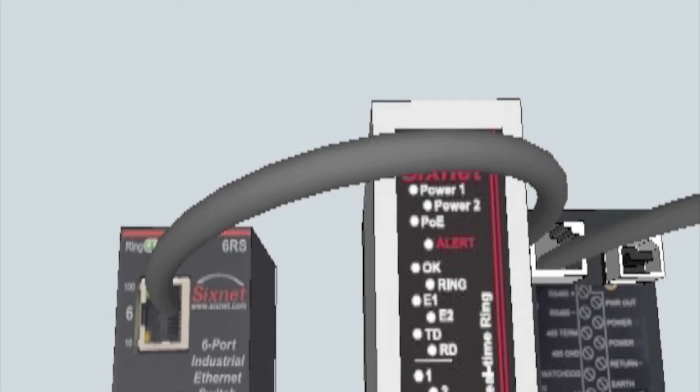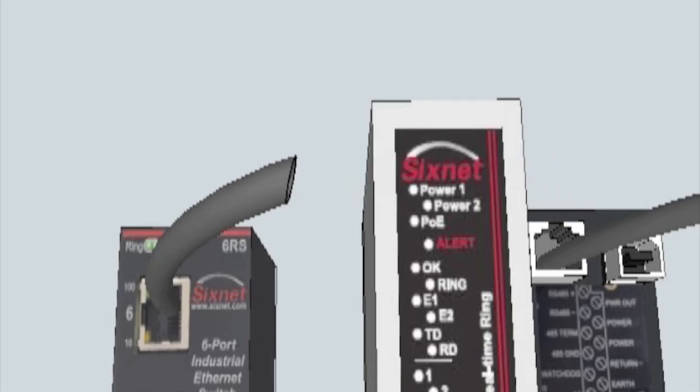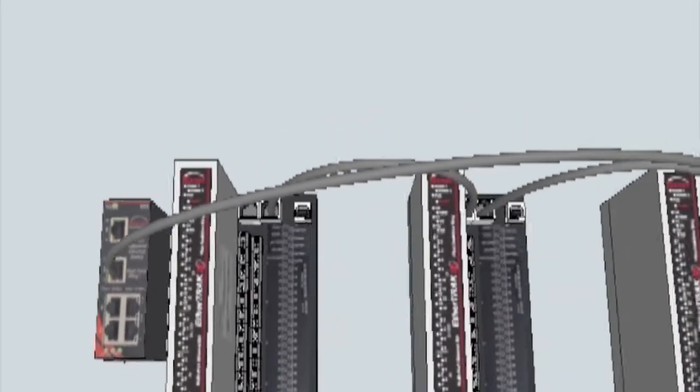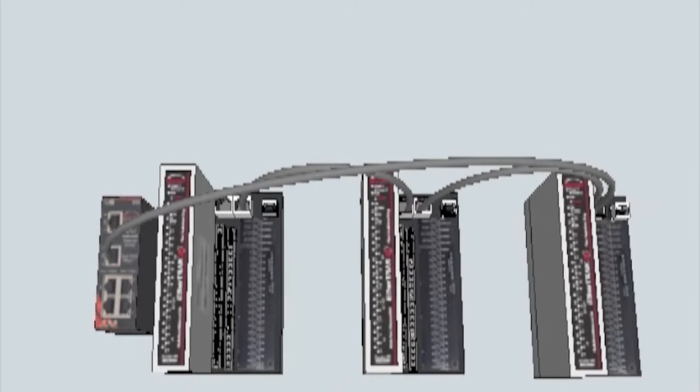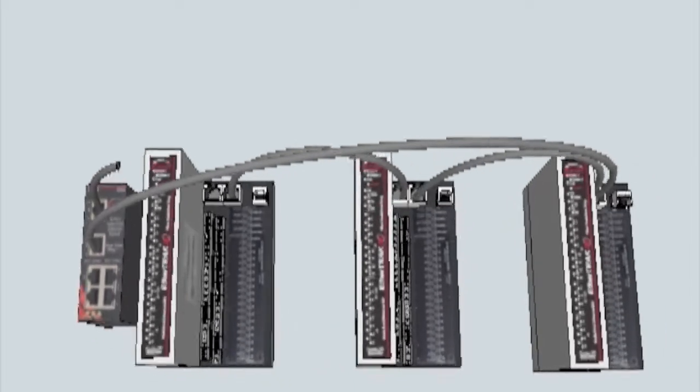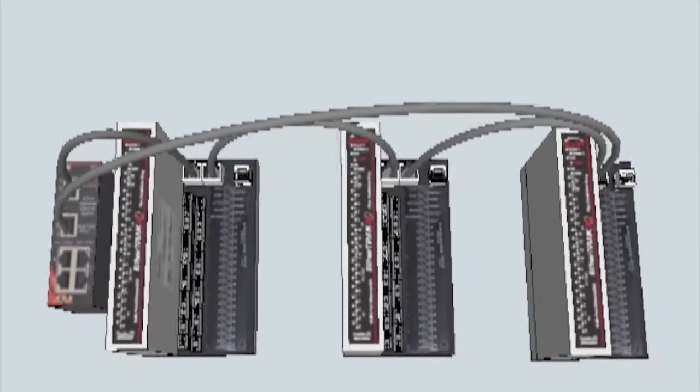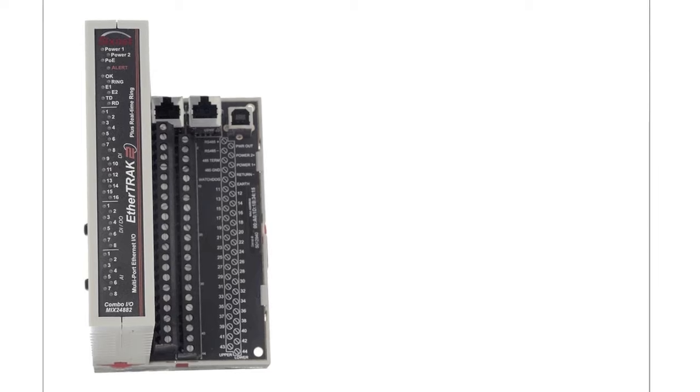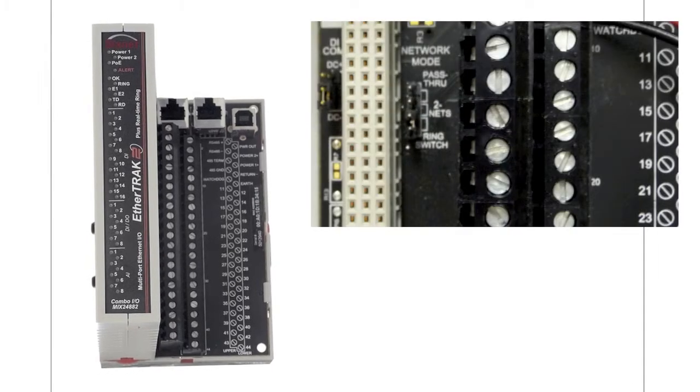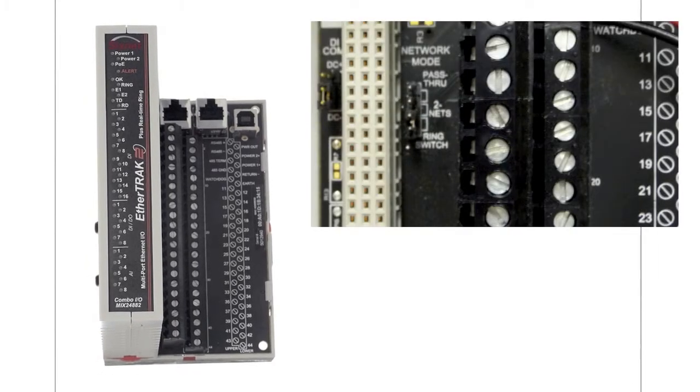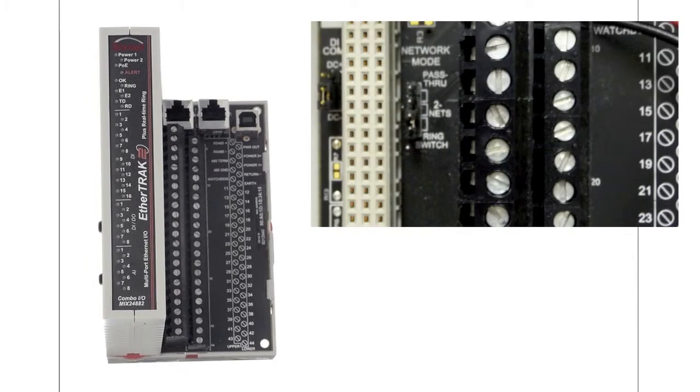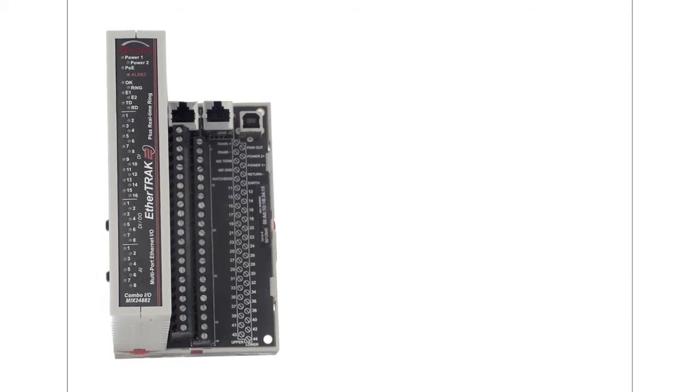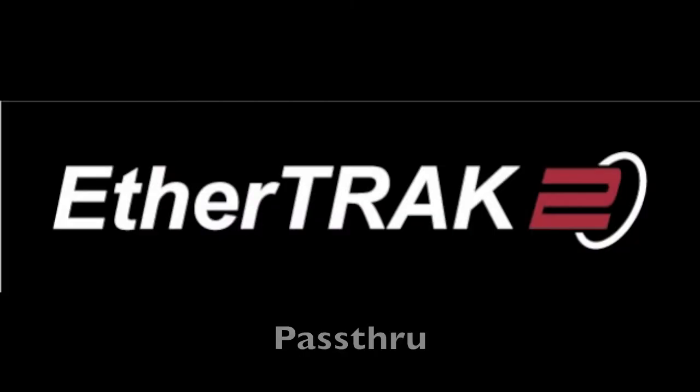This topology should always be used with a Sixnet managed or ring switch because the ring switch algorithm will not be compatible with non-Sixnet switches or personal computers. To configure this option, simply unplug the logic module from the base and change the network jumper to the ring position.